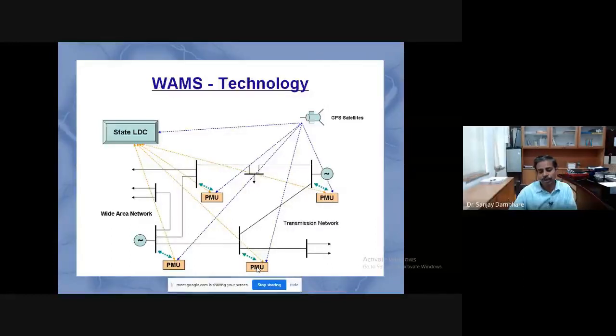So you need to study the controllability and observability of the system. From the controllability and observability of the system, the PMUs are placed on the system at strategic locations, and these PMUs are time synchronized. The timing signal is common, which means GPS is used to give the timing signal to all the PMUs.